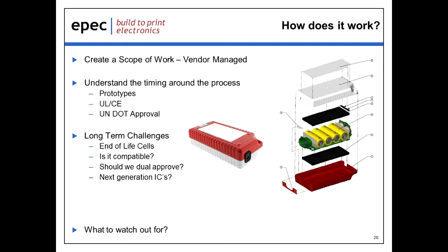And then, is it compatible? One of the reasons that I put the A123 slide up on the last slide was that, as everybody knows, A123 is a pretty high-profile company that had to go through some financial challenges. So the reality is that you can't take one manufacturer's battery and drop it into a design like this and have it work. There's a whole bunch of additional firmware and software things that need to be changed, and you have to go back through the UL and the CE approval.